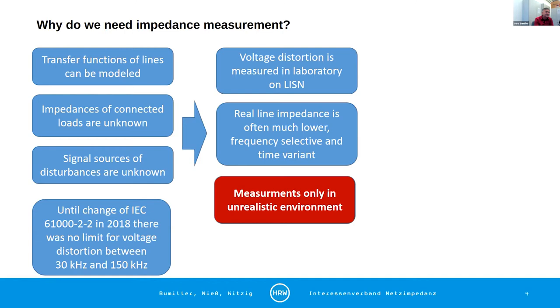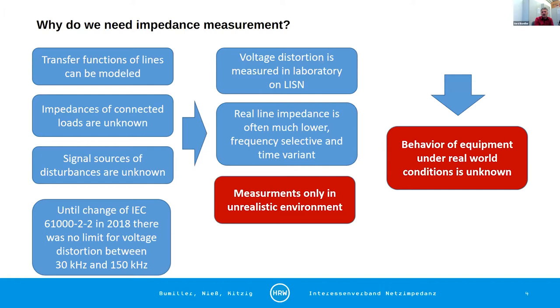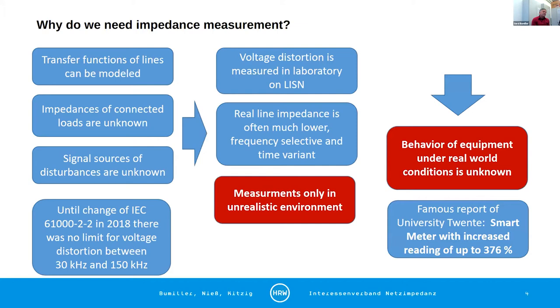What results is that these measurements are only done in unrealistic environment. So if we do measurement on voltage distortions, we do it in an unrealistic environment. We have no idea of the behavior of equipment under real world conditions. I think we had a famous report from the University of Twente where smart meters typically designed for accuracy better than 1% increased reading up to 376%, completely stupid value due to effects. We need better understanding of the behavior of the grid over full frequency range and also for higher frequencies.